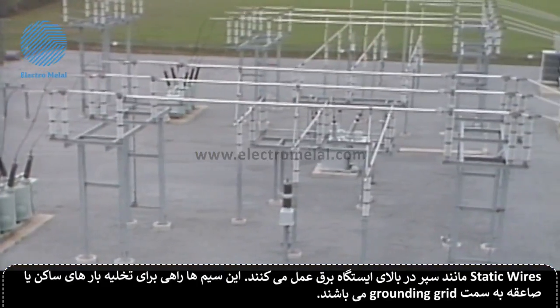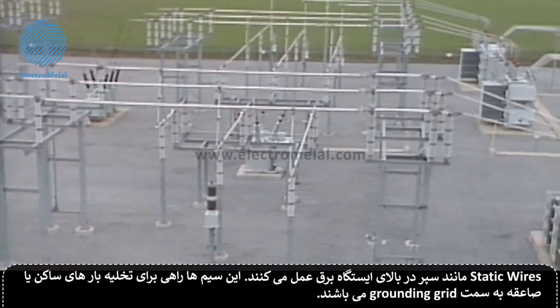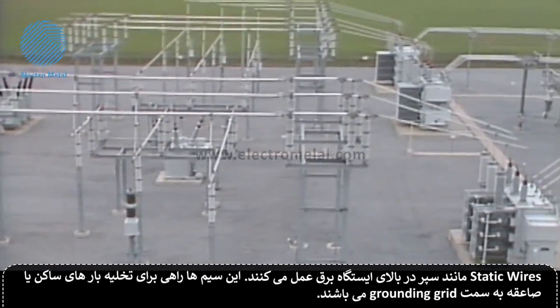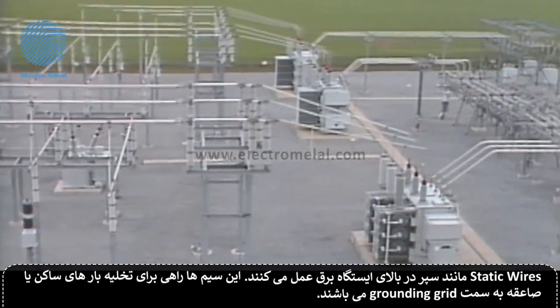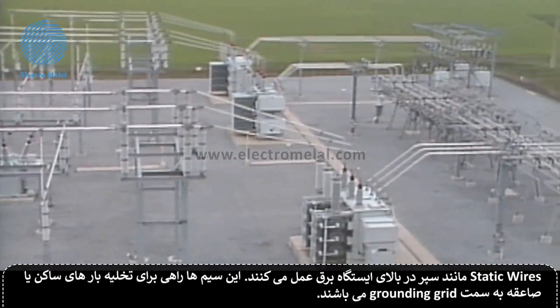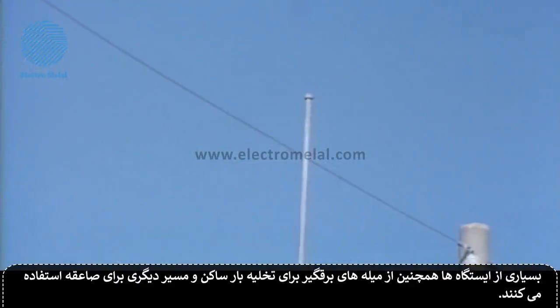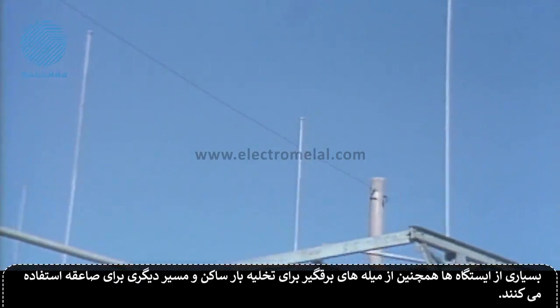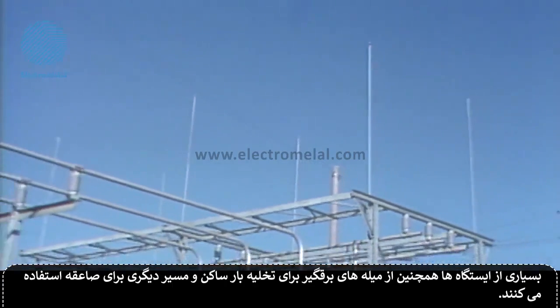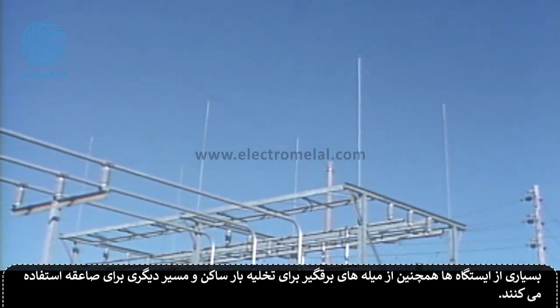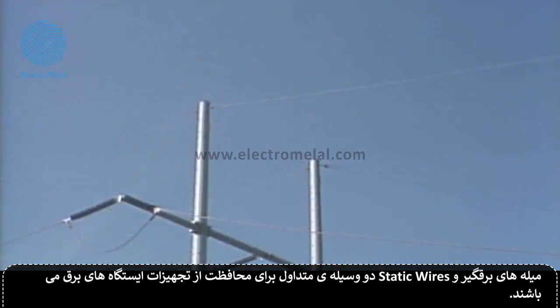The static wires act as a shield above the substation. They provide a path for static charges or lightning strikes to disperse to the earth through the grounding grid. Many substations also use lightning rods to bleed off static charges and provide another path to ground for lightning. Lightning rods and static wires are two common devices used to protect substation equipment.